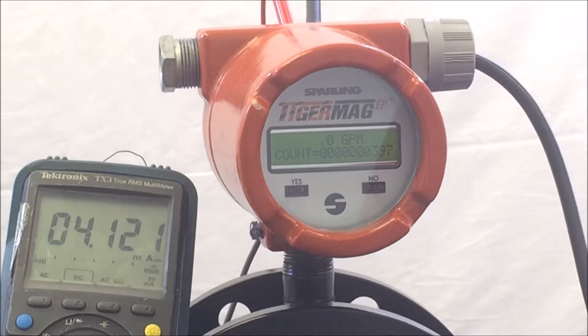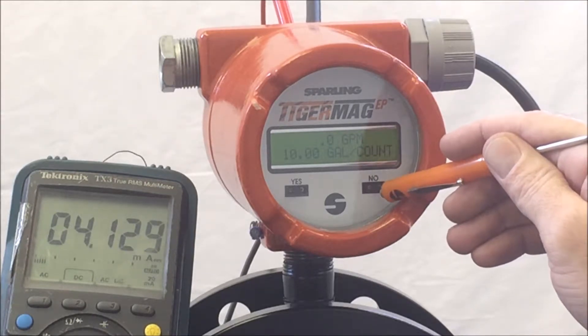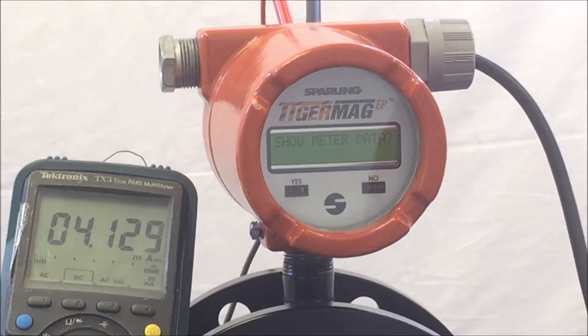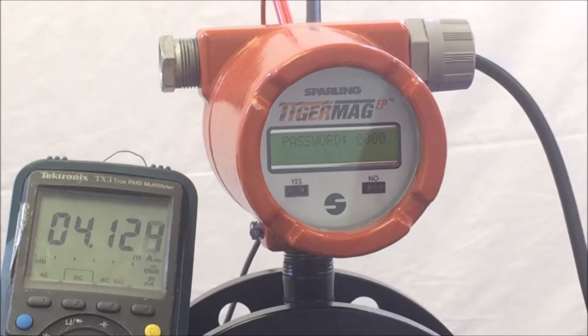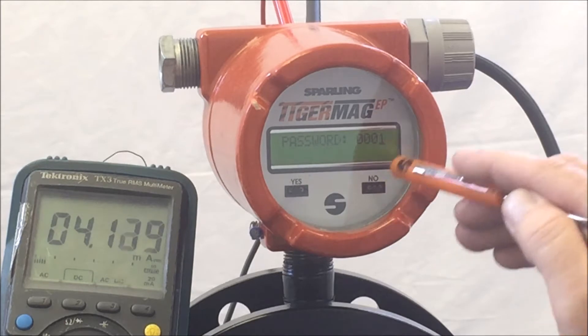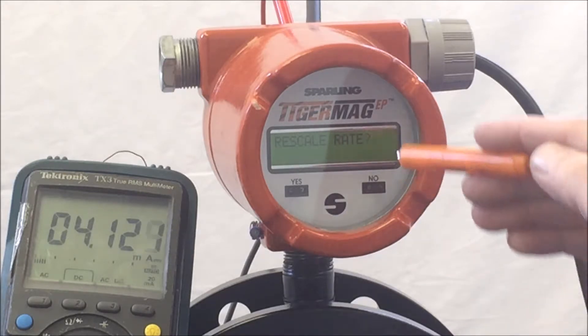This parameter allows you to observe and test some of the critical operations of your meter. Take your magnetic probe or magnetic screwdriver and hold it over the NO side for approximately 5 seconds. The meter will respond 'Show Meter Data.' Hit No to enter the password. Password is 0001 and hit Yes. The meter will respond 'Rescale Rate.' Hit No until the meter gets to Diagnostics.